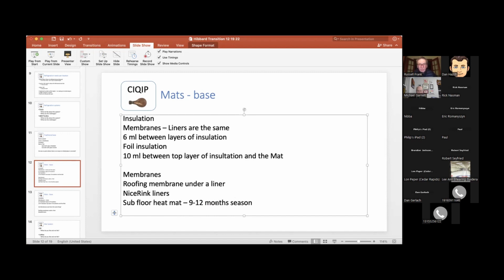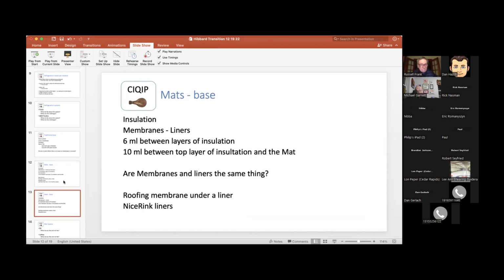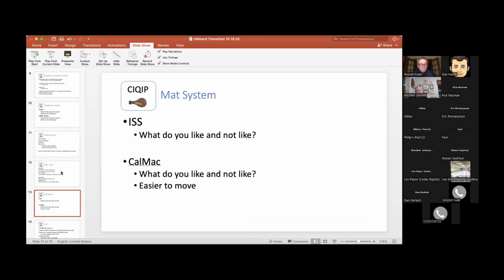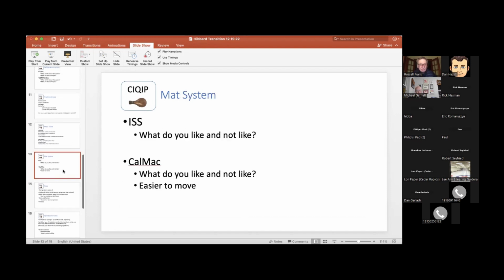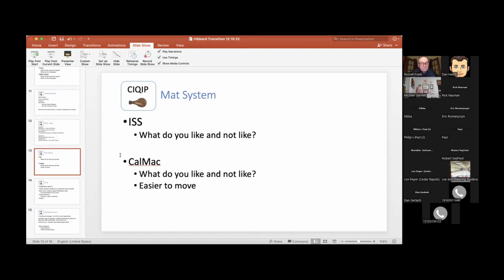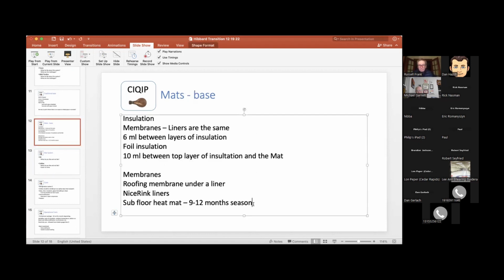The subfloor heat, if you're a 6-month club, you would never need it. But I tell clubs we can get some temperature monitors and put them in the subfloor so you can monitor it. Say it gets near the end of the season and you're having a really good year and want to operate an extra month or two - if your subfloor temperature is 35 degrees, you can do it. You could let it go down to about 27, 28 degrees before you need to start thinking you better get this ice out.